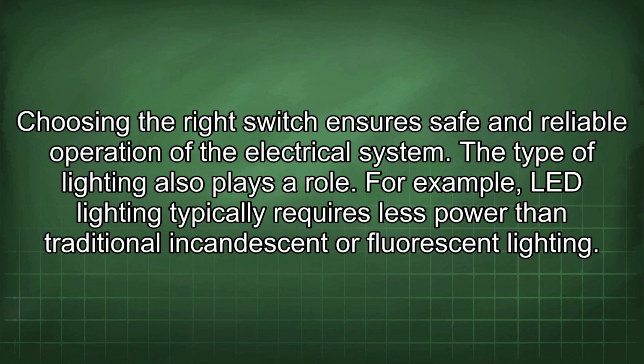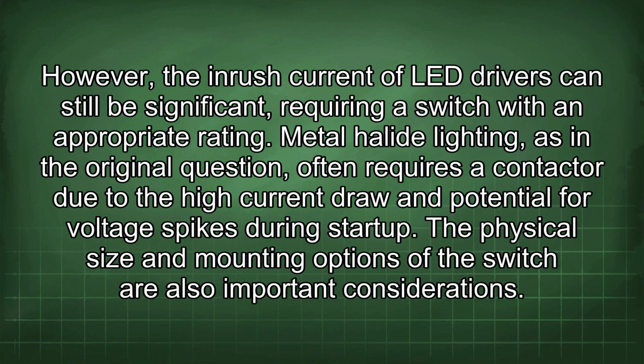The type of lighting also plays a role. For example, LED lighting typically requires less power than traditional incandescent or fluorescent lighting. However, the inrush current of LED drivers can still be significant, requiring a switch with an appropriate rating. Metal halide lighting, as in the original question, often requires a contactor due to the high current draw and potential for voltage spikes during startup. The physical size and mounting options of the switch are also important considerations.